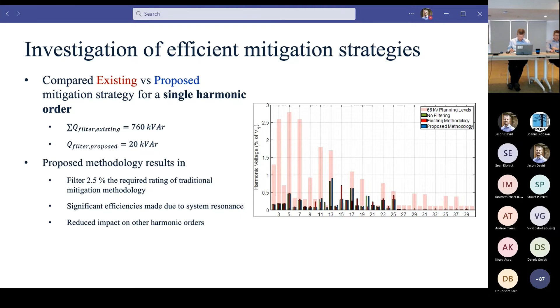And really this efficiency is seen because the current emissions are aligning with a resonance in the network itself. So managing those resonances at the point of resonance is where real efficiencies can be made using this process. And also just to note that because we don't have filters scattered across the network, we ultimately reduce the impact that the filtering has on other harmonic orders, which we'd actually see if we used business as usual. So just a few notes there about comparing the existing and the proposed methodology.